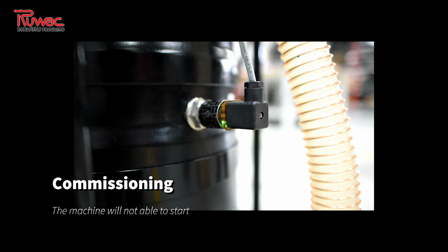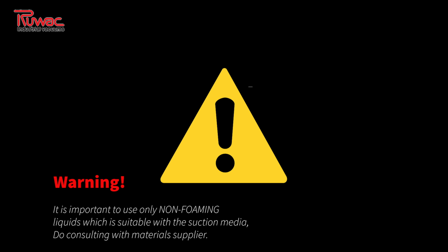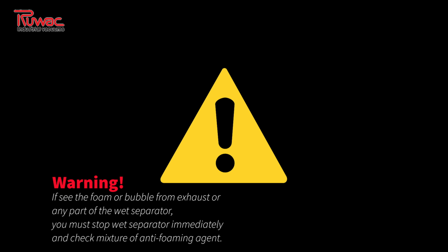Warning: it is important to use only non-foaming liquids which are suitable for the suction media. Do consult with the materials supplier. If you see foam or bubbles from the exhaust or any part of the wet separator, you must stop the wet separator immediately and check the mixture of anti-foaming agent.